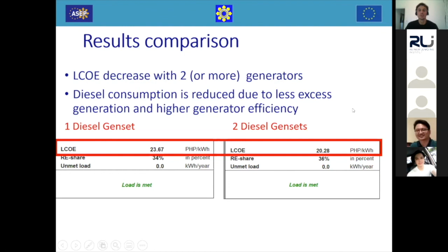So while your system is still running, I can already explain some important differences. What we will find out now is that if we use 2 diesel gensets, the LCOE will decrease. And why is that? Because there's a higher generator efficiency, because both generators can work at a higher efficiency, or for example, if there is very low demand, only one diesel generator will jump on and can work at a higher operation state, load state. And there is less excess electricity generated, so there's less diesel consumed.